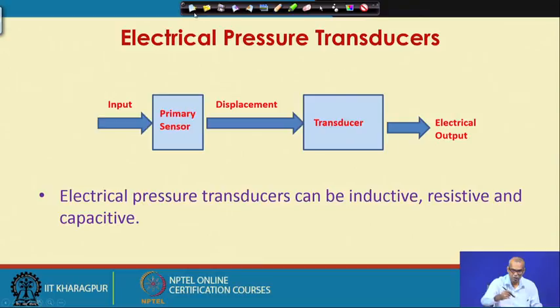As we have discussed while talking about transducers, a transducer element usually gives us an electrical signal as output and it becomes very convenient for the purpose of measurement. Now, several pressure measuring instruments give us displacement as output. Let us say the elastic element types such as Bourdon tube, bellows, diaphragm, they all give displacement when pressure is given as input. So, elastic pressure elements give us displacement or deflection as output when pressure is input.